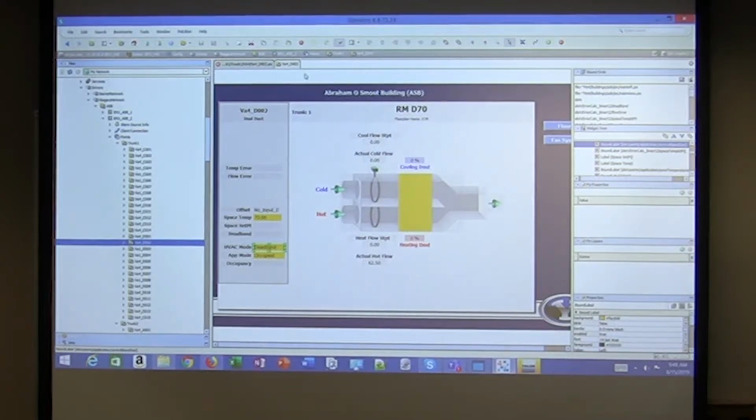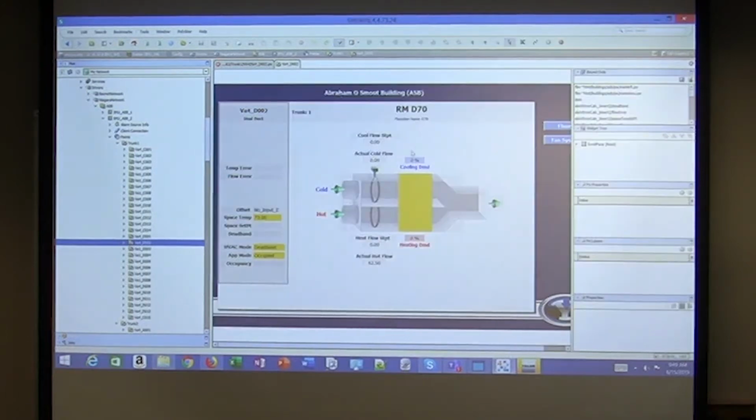What's the purple stand for, do you remember? Manual. Well, somebody's overridden that one, so that's what purple stands for. It kind of passes that through. Okay? In the red? Red is usually an alarm, but in this instance, I think somebody just used a blue background and a red background. That's not actually doing anything. So if we peek at the graphic, you'll see up here background blue and no color effect. Okay?